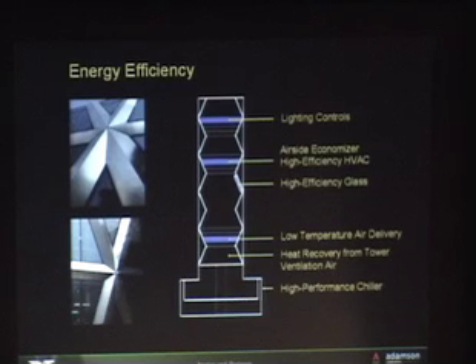On this building, we elected to go with large built-up AC units to serve the building as central units instead of locating systems on each floor. When the temperature outdoors is less than the space indoors, you get a tremendous amount of free cooling. When the temperature is below 55 degrees, which is most of the year in New York, you cool the building for free, which is a good thing. It's very energy efficient.